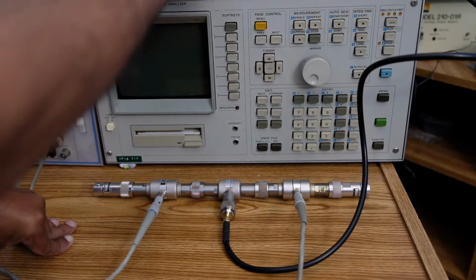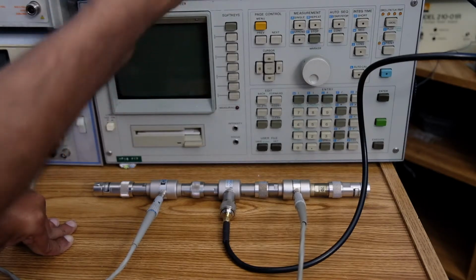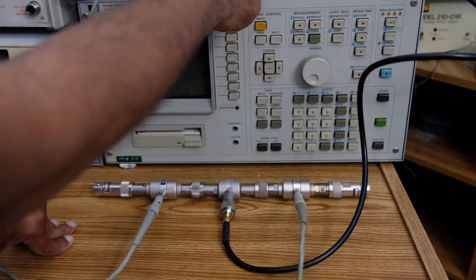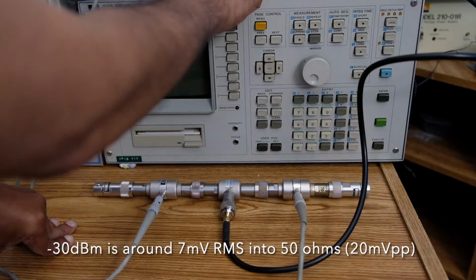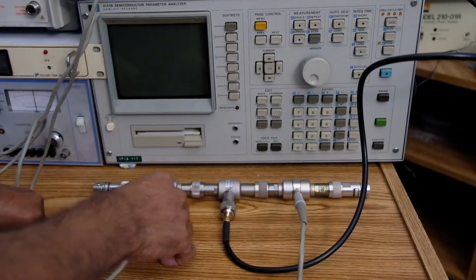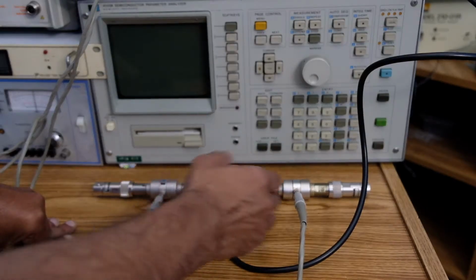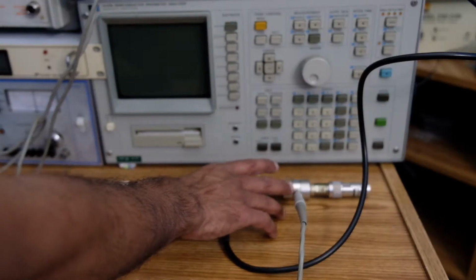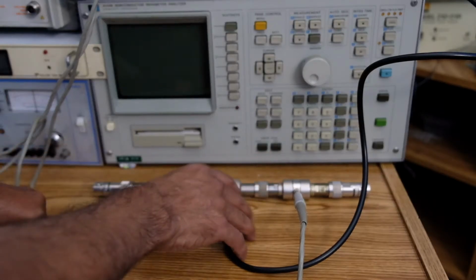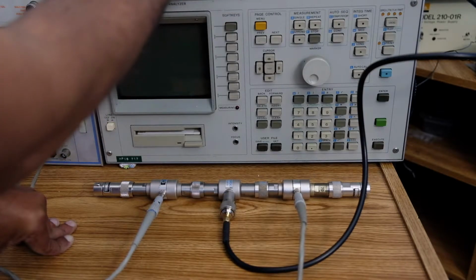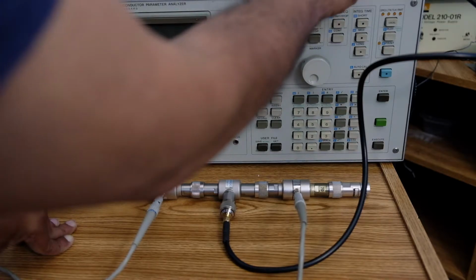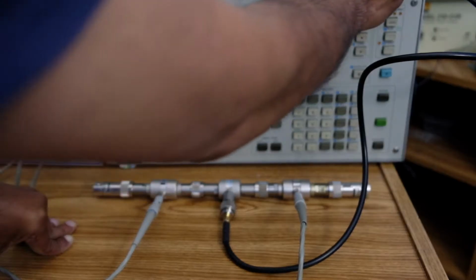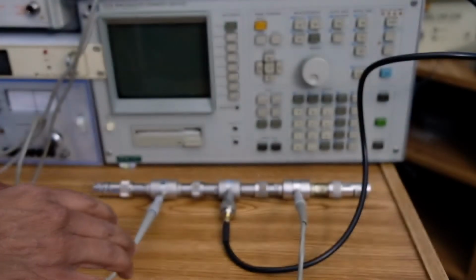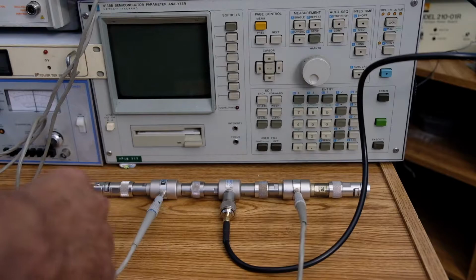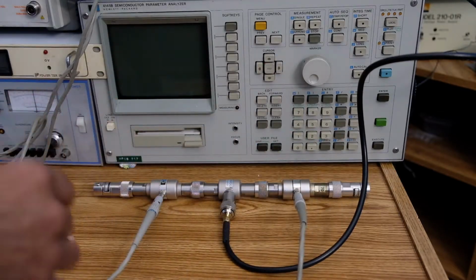That means it's locked. And you can see it on channel A, the amplitude is in the minus 30 dBm range, and you can compare the signal on both A and B, and they should be equal because there's no difference in the length of the cable or in this section, and A and B, ideally in a well calibrated instrument, should be about the same. So as you can see, there's no difference in the amplitude on channel A and B, and the phase difference is already set at 0 and nulled, so it's right now at 0 degrees. So that is a perfectly equal signal on both channel A and B. There's no phase delay, there's no mismatch in any way.